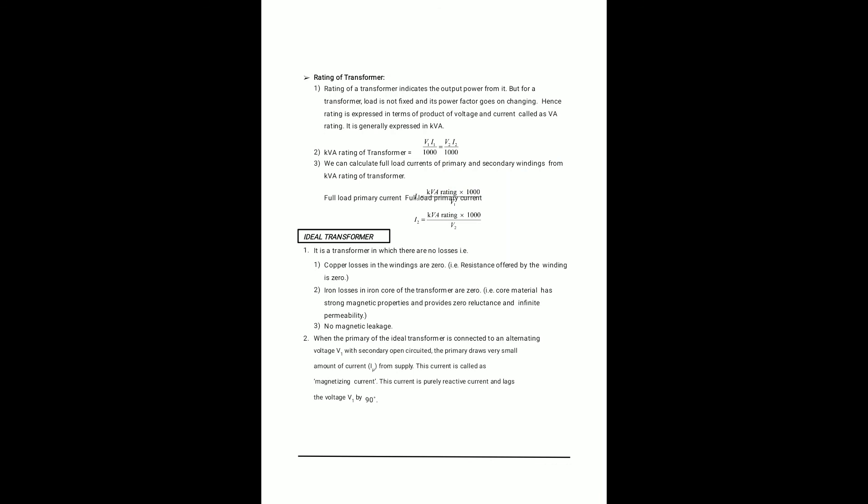The rating of a transformer indicates the output power. Since the load and power factor can change, the rating is expressed as the product of voltage and current, called the VA rating, expressed in KVA. KVA = V1 I1 / 1000 = V2 I2 / 1000. The full-load primary current I1 = KVA rating × 1000 / V1, and the full-load secondary current I2 = KVA rating × 1000 / V2.